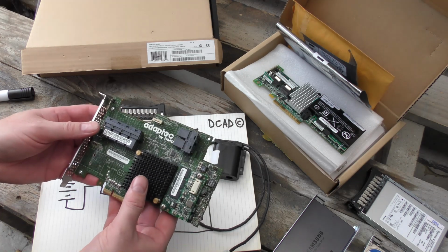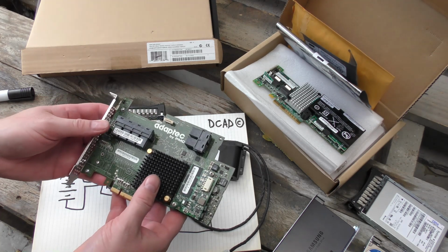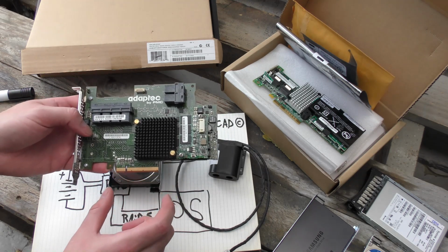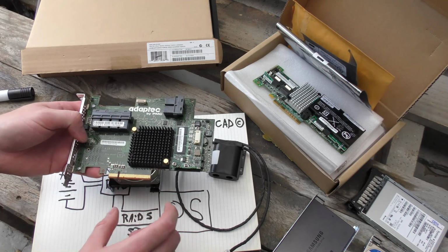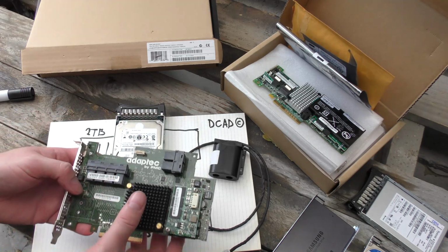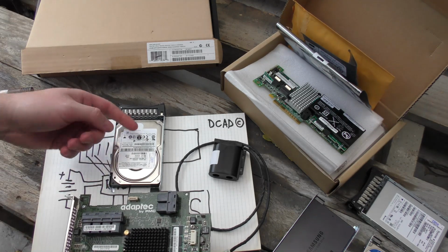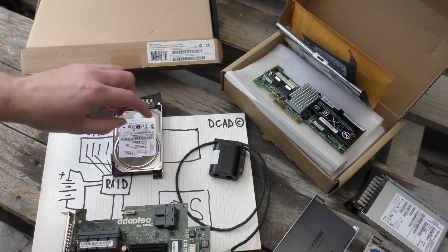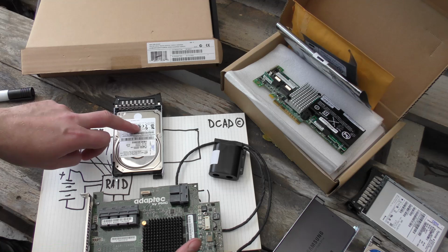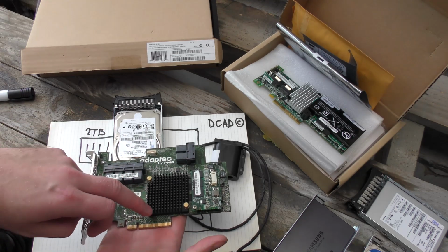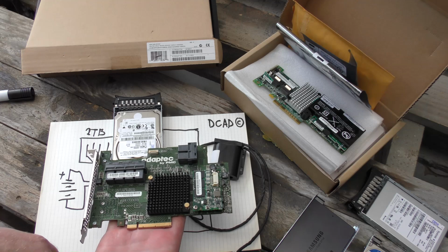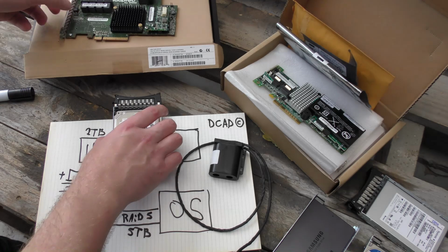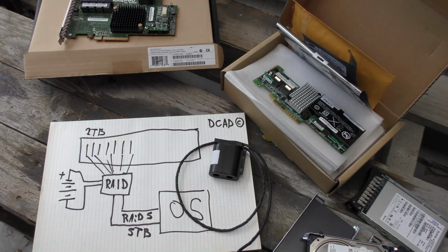It's nothing that you would ever have to think about, but it means a lot that as soon as the RAID controller sees the data from the operating system, it will just say, I got it, instead of having to write it to the disk out here. The disk has a lot of electronics on the back as well, so the disk will tell the RAID controller, I've received the data, and then the RAID controller could tell the operating system, yes, we have the data. This is something that it does to prevent data loss in the event of a power failure.